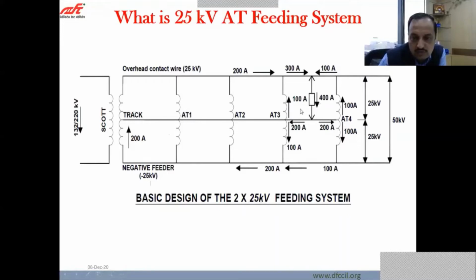The main advantage of this system is that whenever a locomotive with a train is moving in a particular stretch of the section, the maximum current sharing is done by only these two auto transformers. So the net current in these conductors gets reduced, because around 50% of the current is circulating, depending on the location of the train. Let us say 50% of the current is distributed here only. So the total current flowing from the traction substation in the conductors is reduced to 50%. So we can say that the voltage drop is reduced, along with other associated benefits of the system.